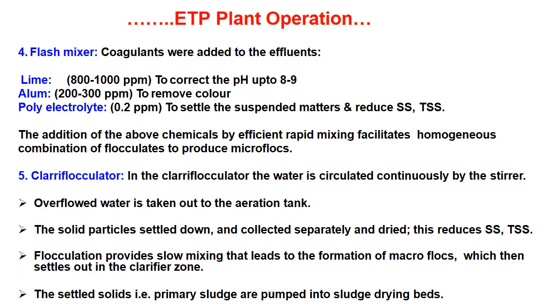Number four is the flash mixer, where coagulants are added to the effluents. Lime at 800 to 1000 ppm is added to correct the pH up to 8–9 when the effluent is acidic. Alum at 200 to 300 ppm is added to remove color and help in flocculation. Polyelectrolyte at 0.2 ppm is added to settle suspended matter and reduce SS and TSS. Efficient rapid mixing of these chemicals facilitates homogeneous combination of flocculants to produce micro flocs.